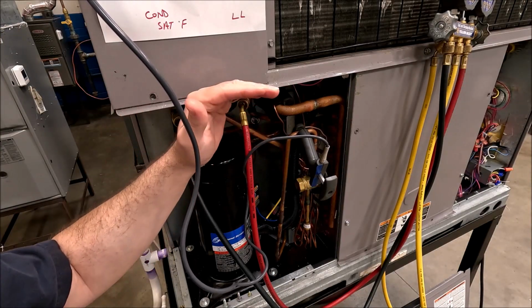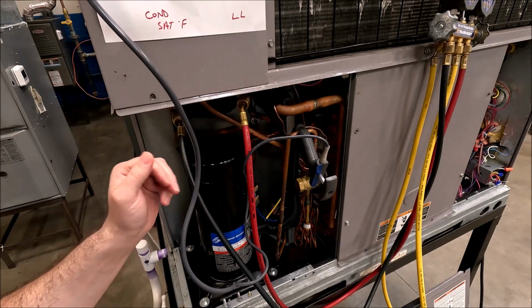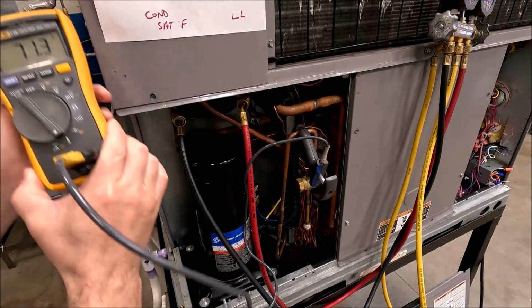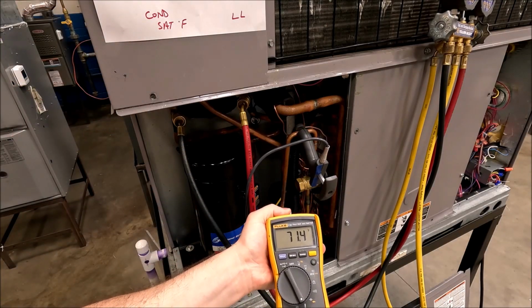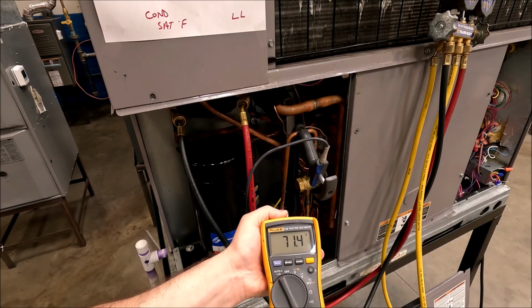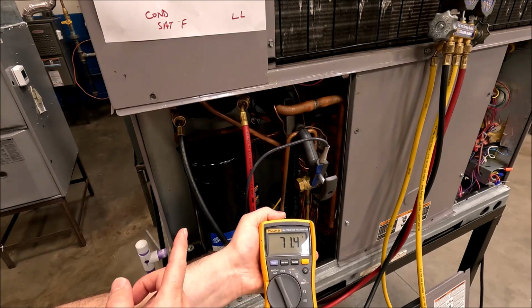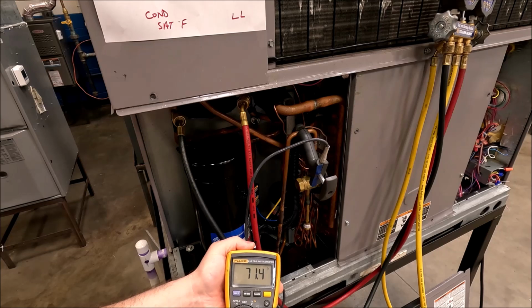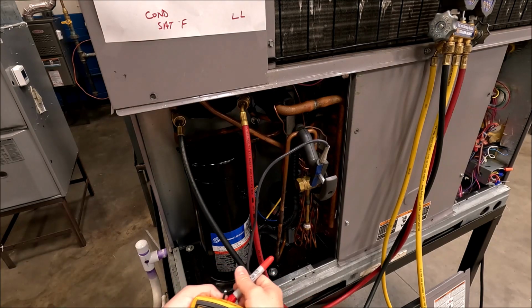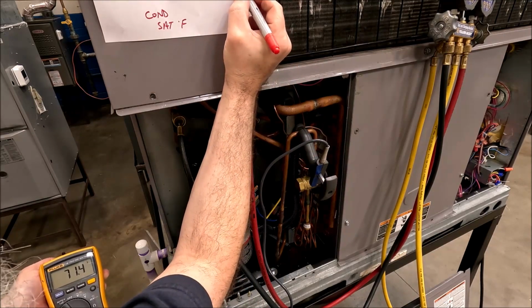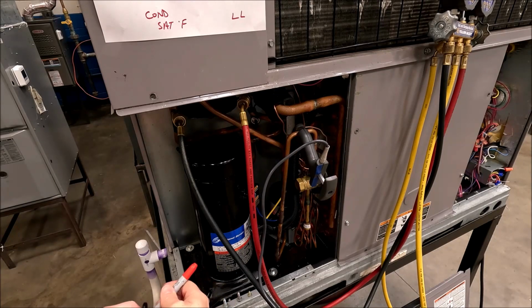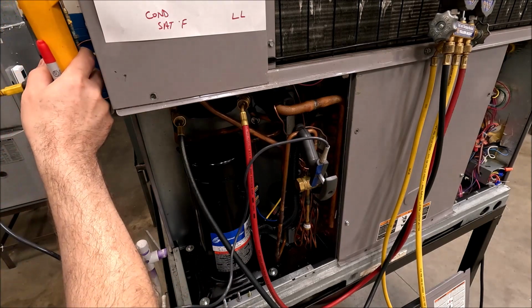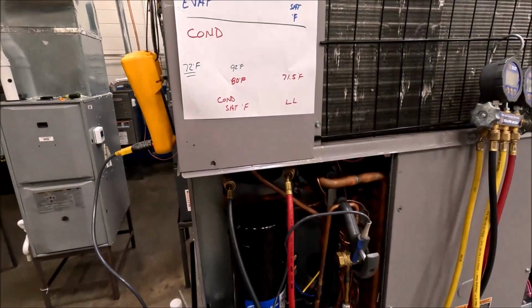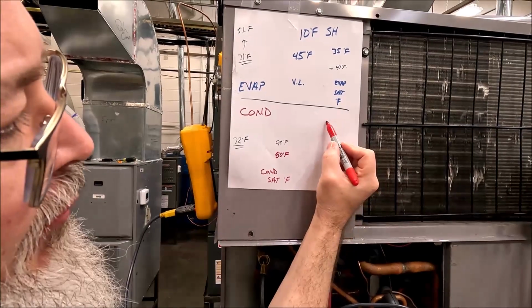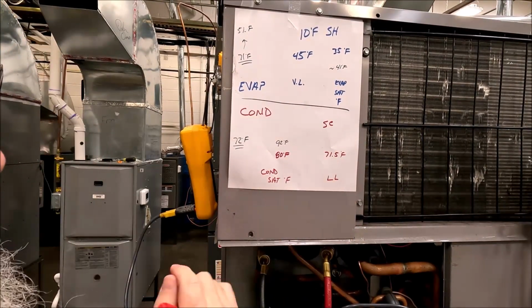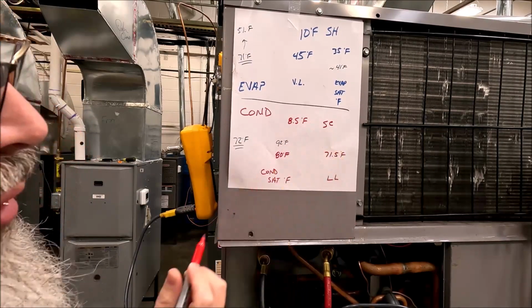Subcooling, by definition, is going to be your condenser saturation minus your liquid line temperature. So we look right here, you can see now I've got between 71 and 72 degree line temperature. That's the liquid line. So if we had an 80 degree coil before, and then we get this 71.5 degree liquid line, well, I've cooled down below saturation, so we could easily do the math and figure out our subcooling value. 80 minus 71.5, you're going to be looking at somewhere of 8.5 degrees.